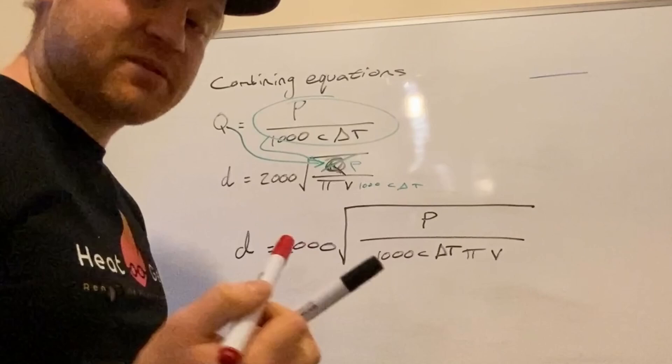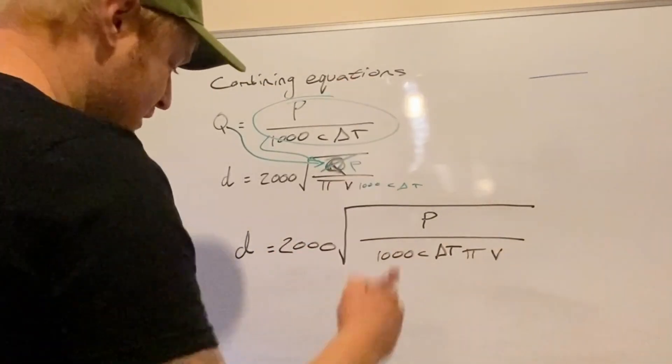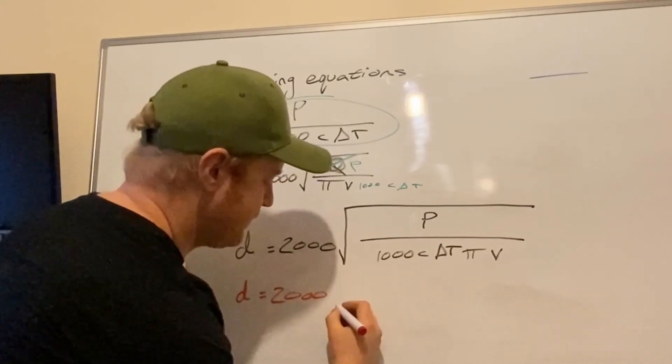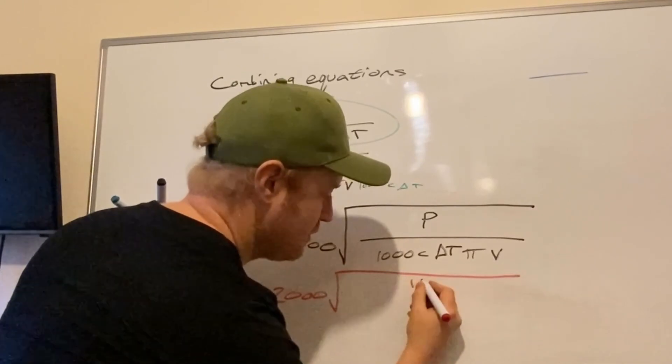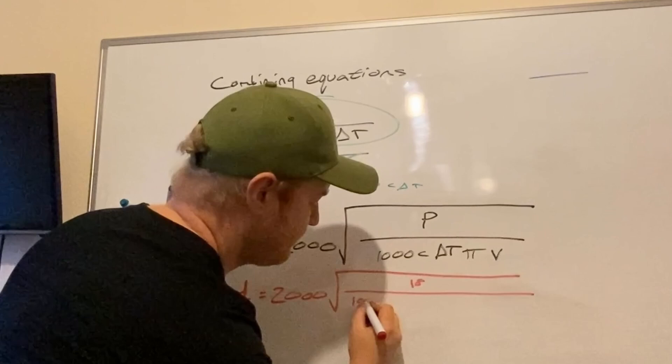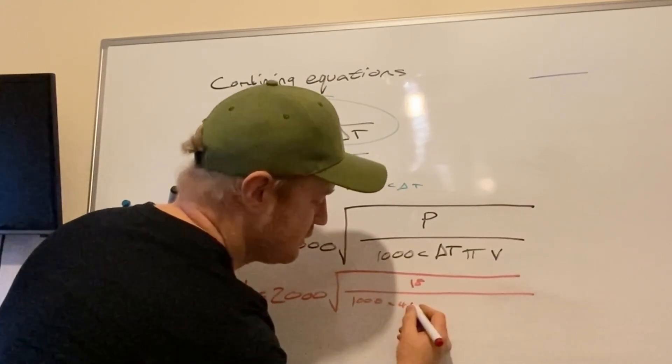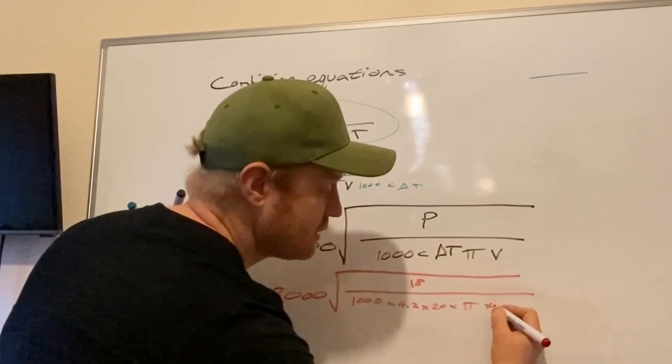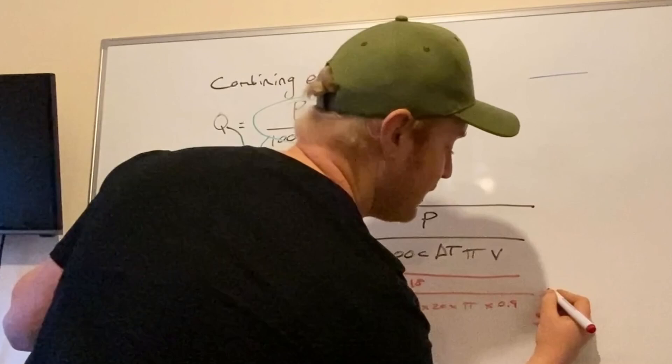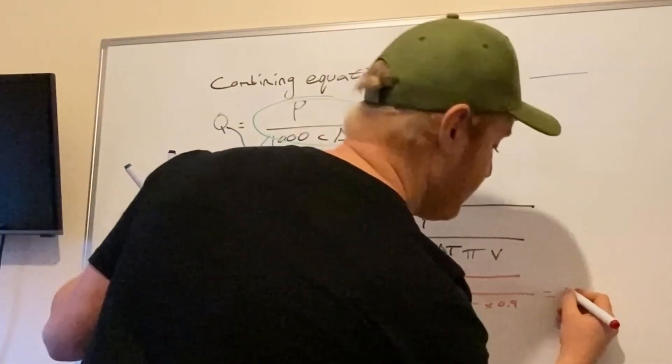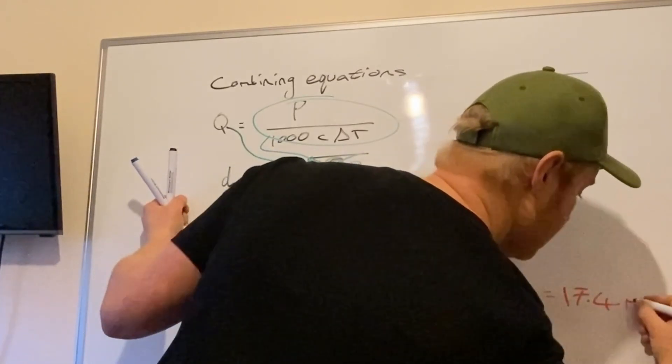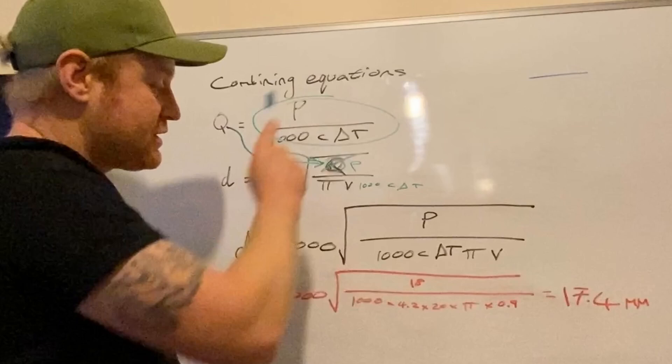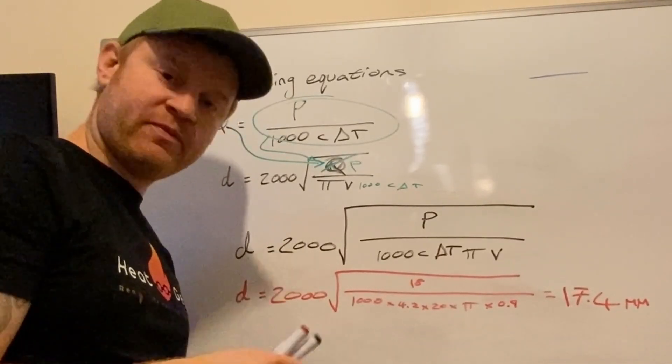You can work it out. Trust me, it works out. I've done an example. And the example is using 18 kilowatt, which was two thousand times the square root of 18 kilowatt divided by a thousand times 4.2 times dT 20 times π times 0.9, and this came out to 17.4 millimeters. So that equation there was found by combining equations. And yeah, highly recommend saving that one. Hope it helped.